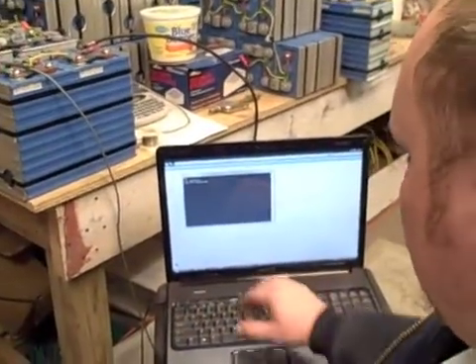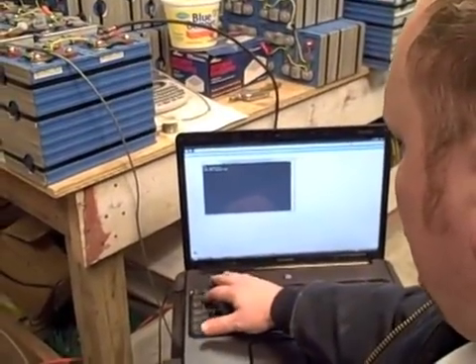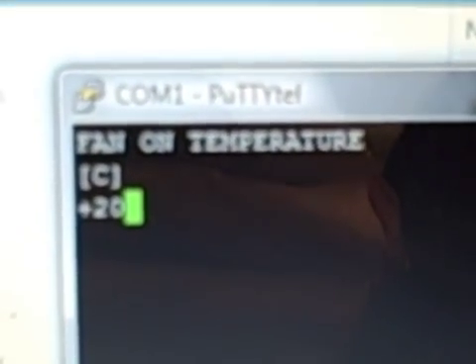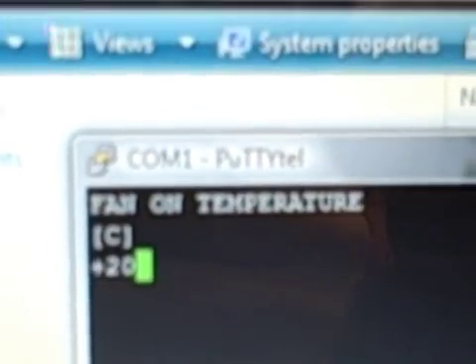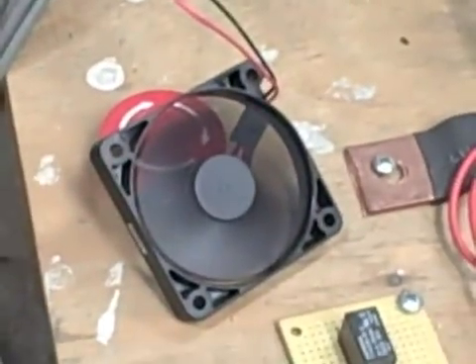I'm connected to our battery management system. The on-temperature right now is set at 20 degrees Celsius. The ambient temperature is roughly 14 degrees Celsius. So I'm going to change it to 13 degrees Celsius and see if that's cold enough to turn the fan on. And if you'll notice, the fan has started running.